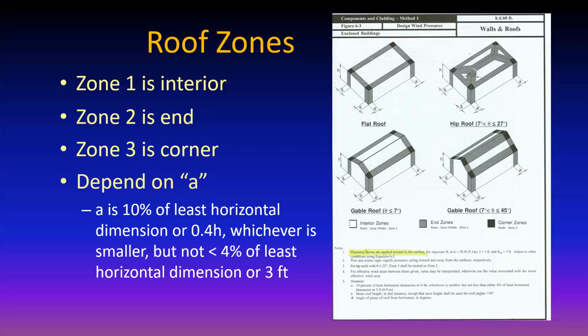There's this parameter A. And okay, so fine. The width of that zone 2 depends on the parameter A, which is 10% of the least horizontal dimension, or 4/10 of the height, whichever is smaller, but not less than 4% of the least horizontal dimension, or 3 feet.